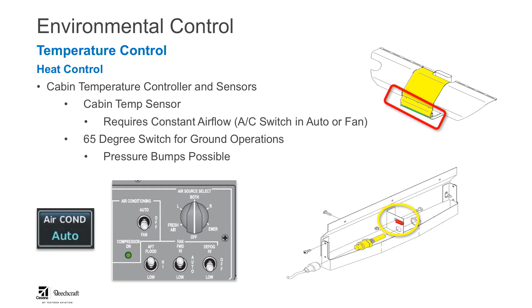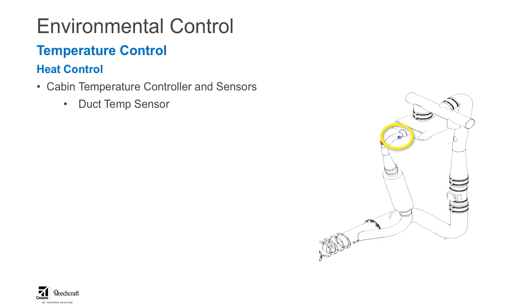All right, going back to the tail cone, we have the duct temp sensor. In order for the controller to understand what the situation is, it needs to look at the cockpit input of where you've selected the temperature. It needs to look at what's actually in the cabin using the cabin temp sensor, and we need to look at what the output of that heat exchanger is. So the duct temp sensor is just downstream of that heat exchanger, as well as the air duct overheat switch. We want to alert the crew if that air duct is getting hotter than about 310 degrees, because that can cause some concern with the ducting.